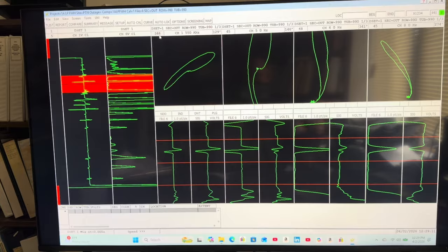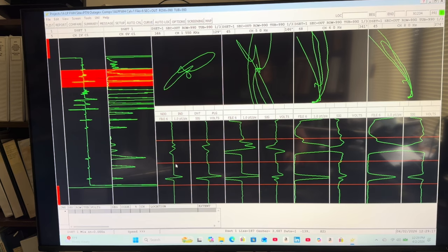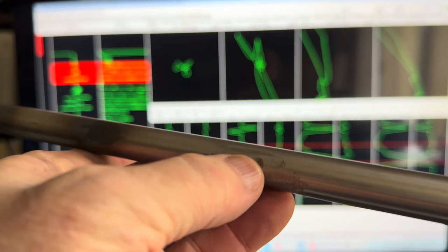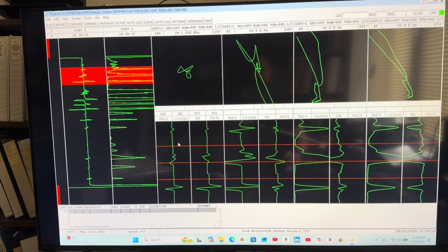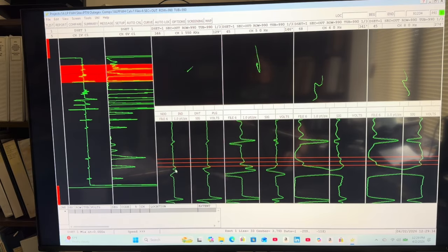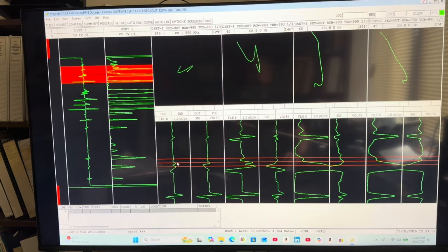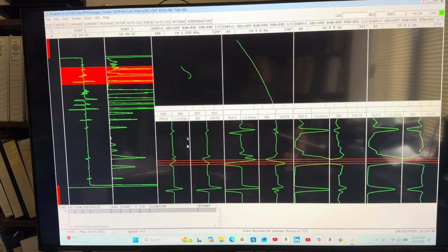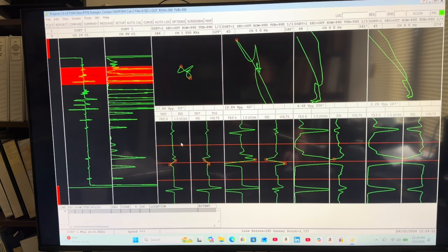Then I took a buffing wheel, some sort of abrasive wheel, and made some scratches. And then in the middle of it, I put another one of those deeper wear flaws in there. Now, what's interesting about this one is you've got two distinctly different phase angles going on here. The shallow, or the high phase, indicating shallow percent through wall depth, is probably from the buffing wheel, the abrasive wheel there. And then right in the middle of all that, you've got this thing that's very deep. So that's probably close to 100% there, not quite all the way through.